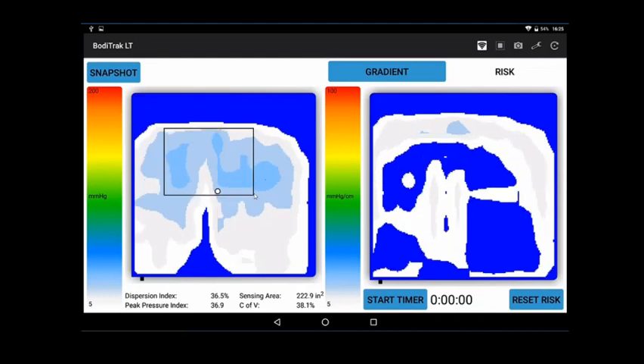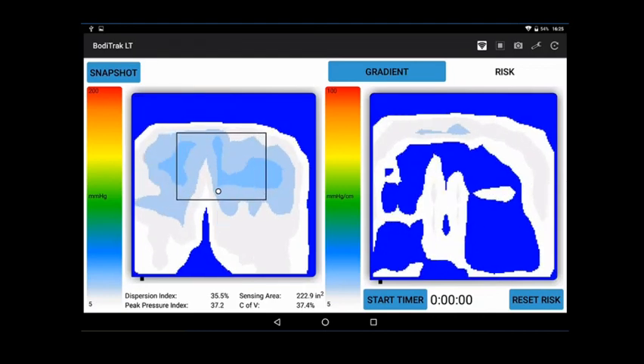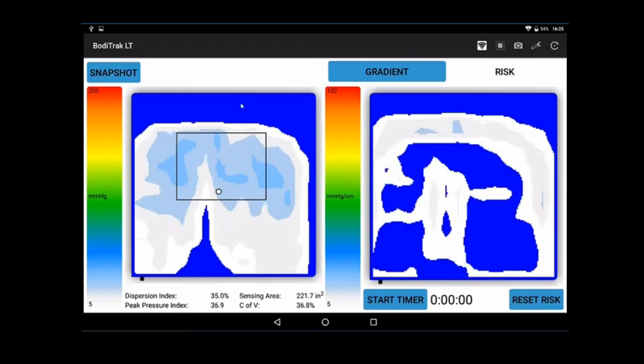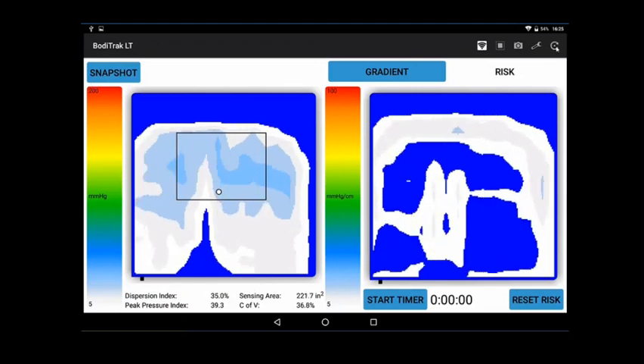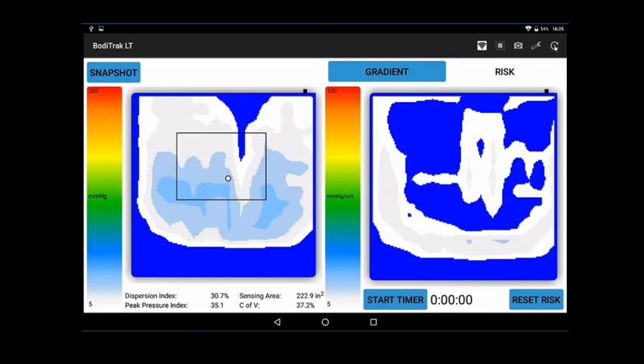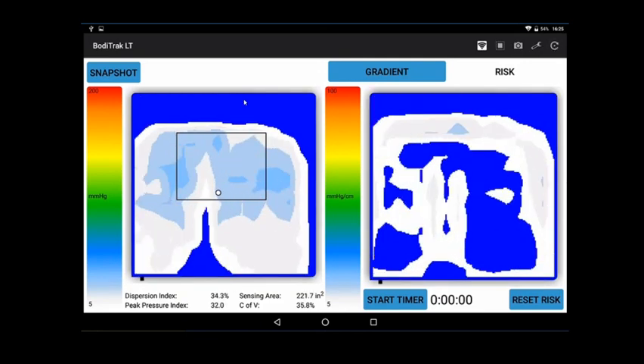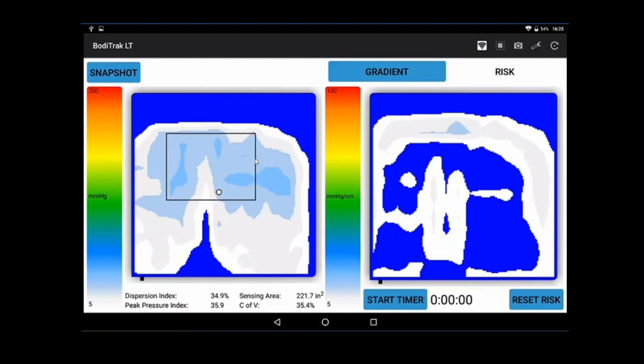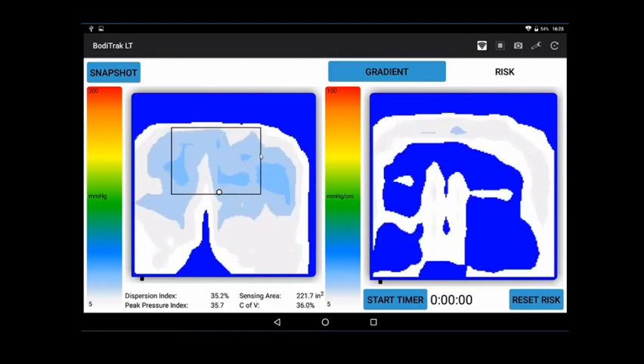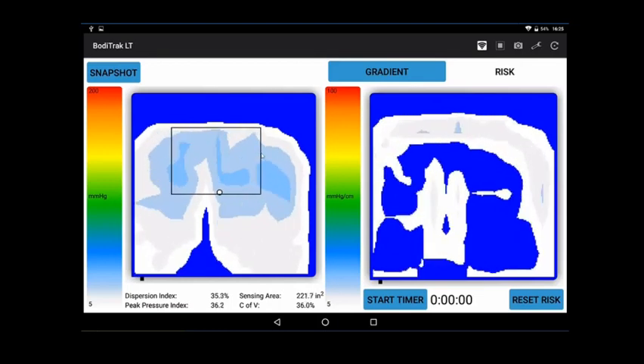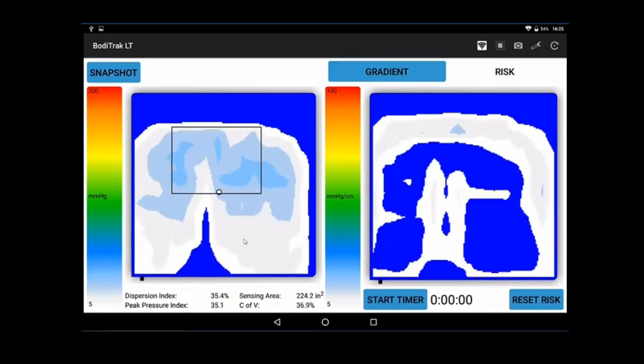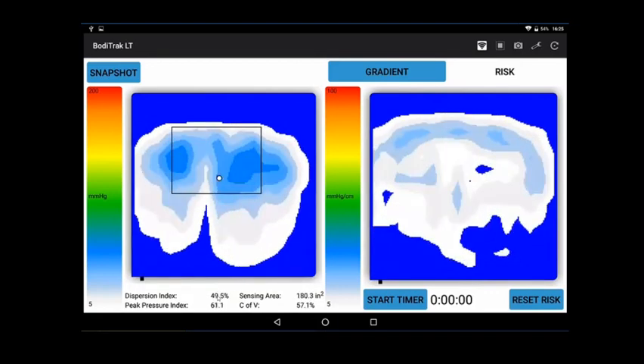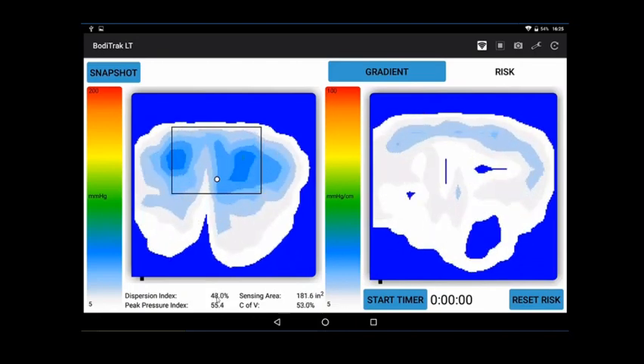This is a traditional pressure map most people have seen elsewhere. The scale is 0 to 200 millimeters of mercury. You've got the ability to rotate the image depending on which perspective you want. This is known as a dispersion index box, so I can position this to capture the ITs and the ischial or sacral area. If that percentage of load is above 50%, then you're at risk of pressure trauma according to the literature.